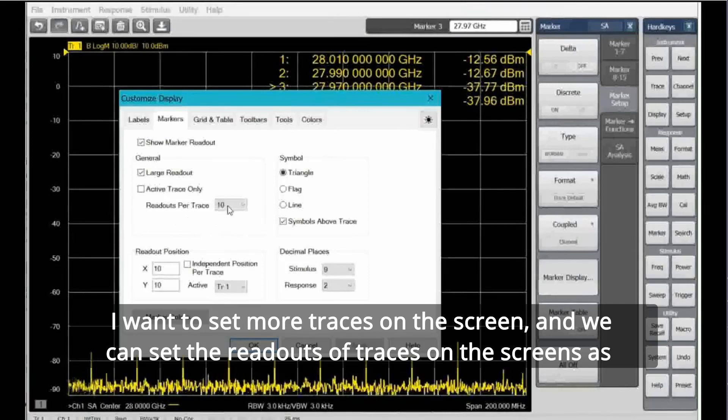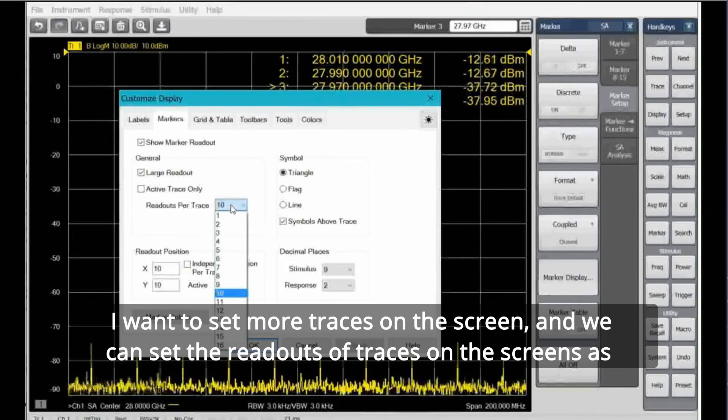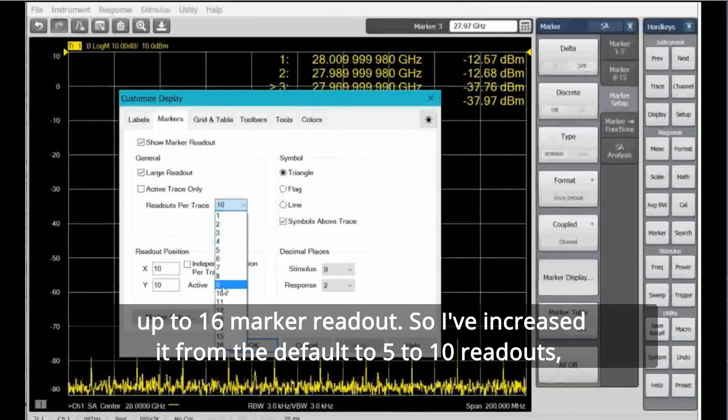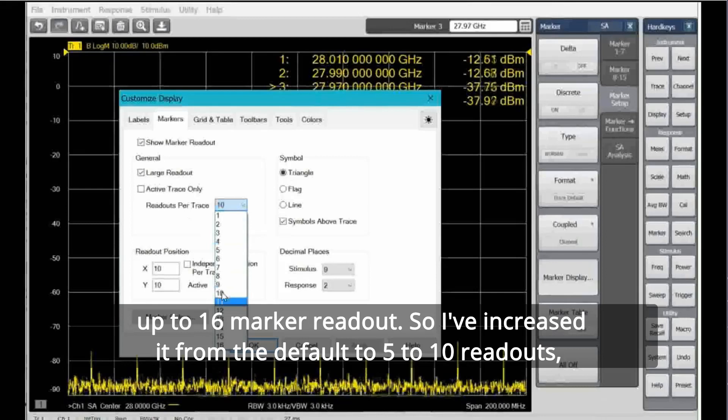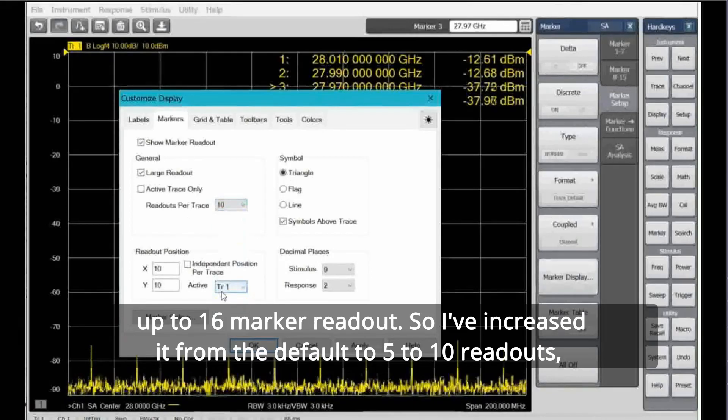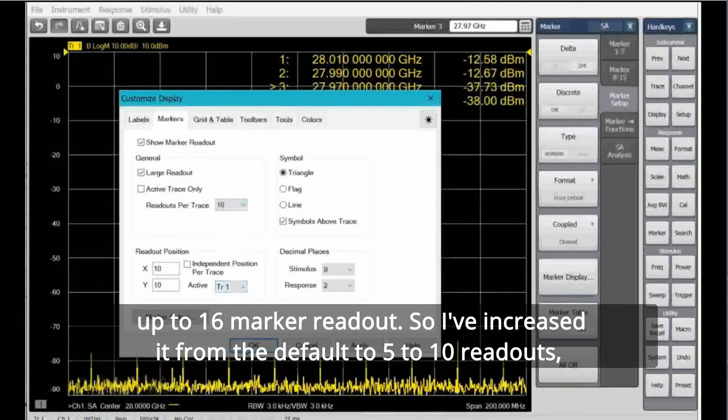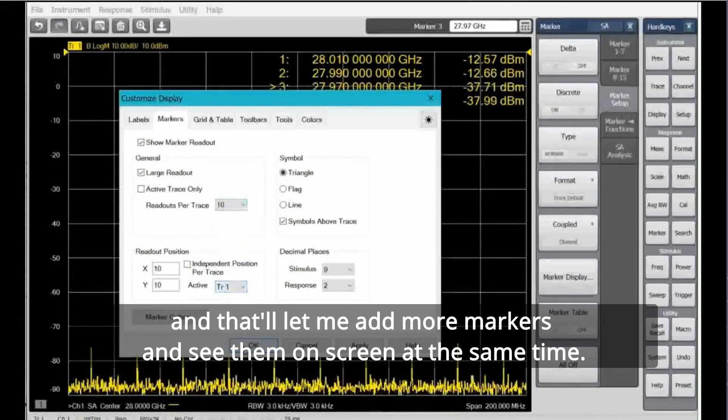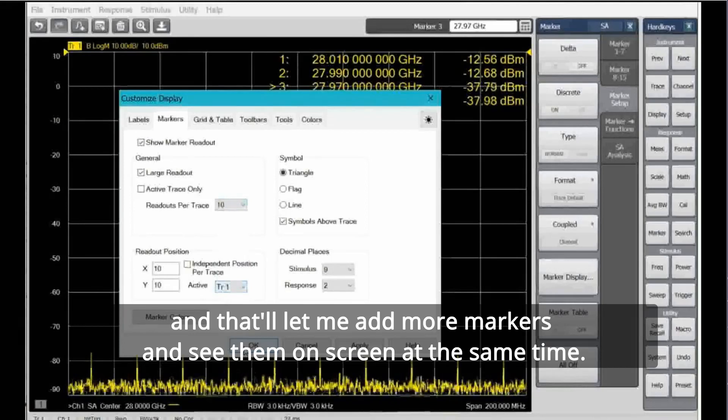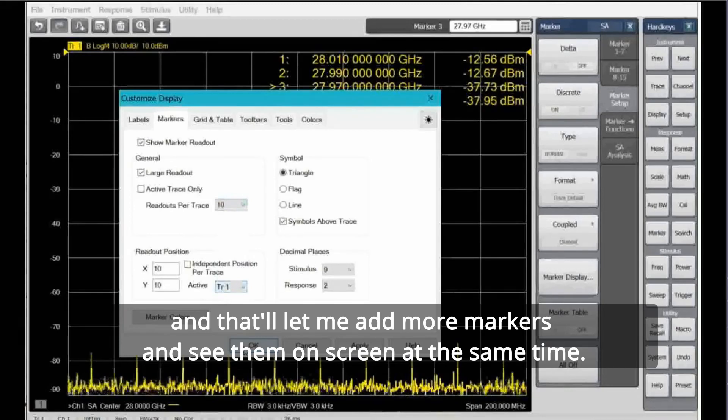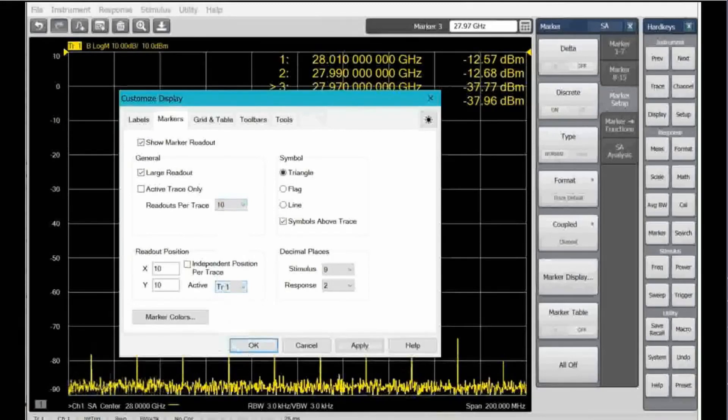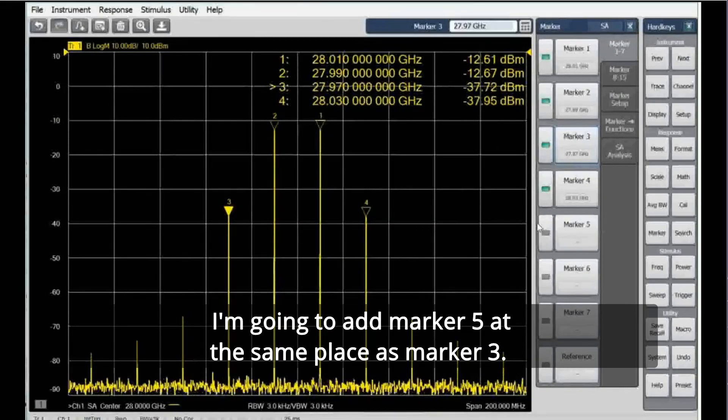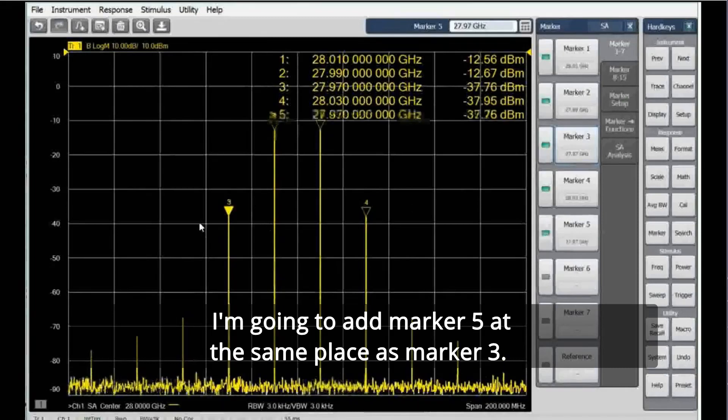I want to set more traces on the screen, and we can set the readouts of traces on the screen to up to 16 marker readouts. So I've increased it from the default of 5 to 10 readouts, and that'll let me add more markers and see them on screen at the same time. I'm going to add marker 5 at the same place as marker 3, I'm going to add marker 6 at the same place as marker 4.